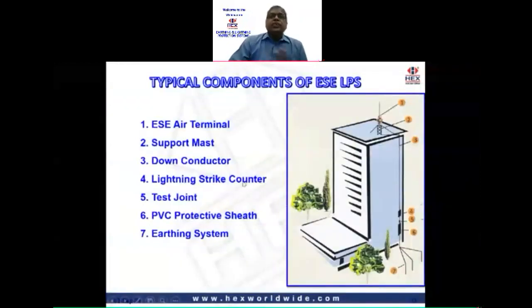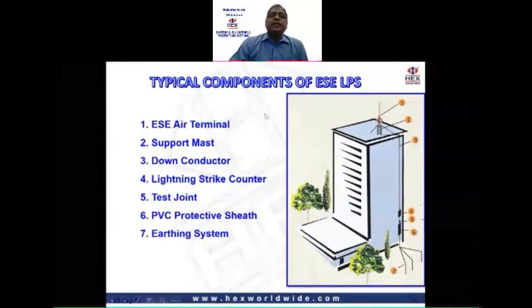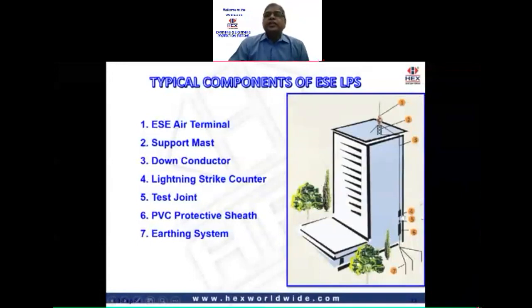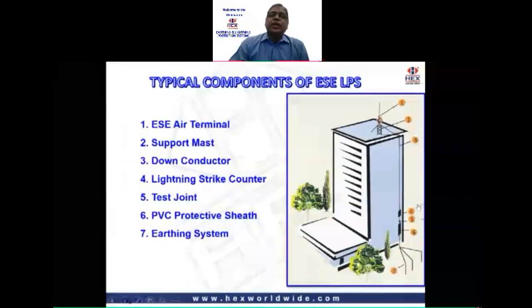These are the typical components of an ESE lightning protection system. The LA or the air terminal is fitted on the top of the mast as per the required height given in the standard. Then you have the down conductor, which provides a safe path to the grounding of the lightning strike. This could be either a bare GI or a copper strip mounted on appropriate insulators, or an insulated copper cable. In between, there is a lightning strike counter, which counts the number of strikes that have taken place on the LA.